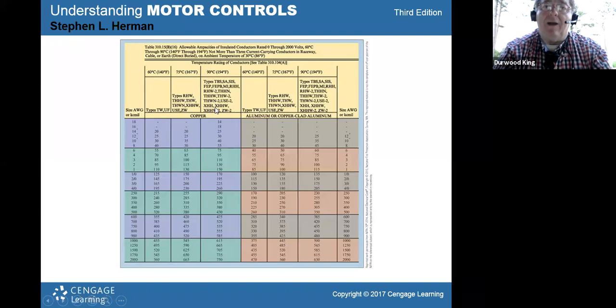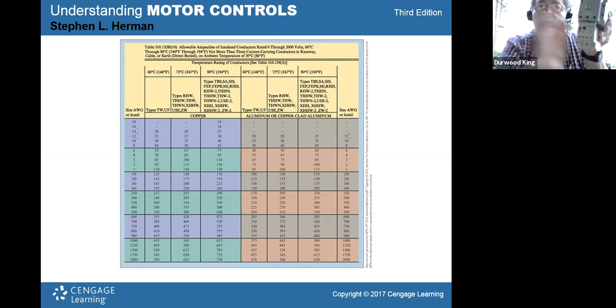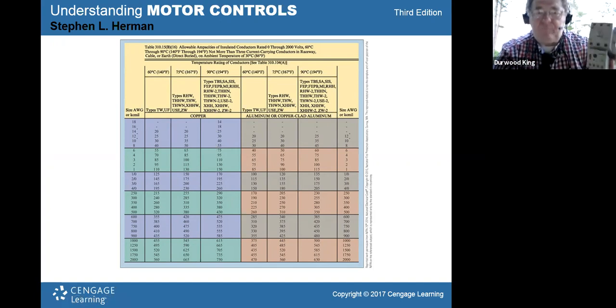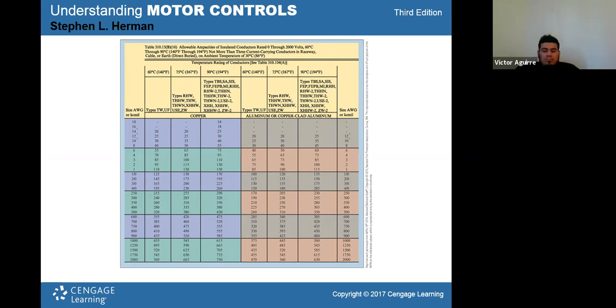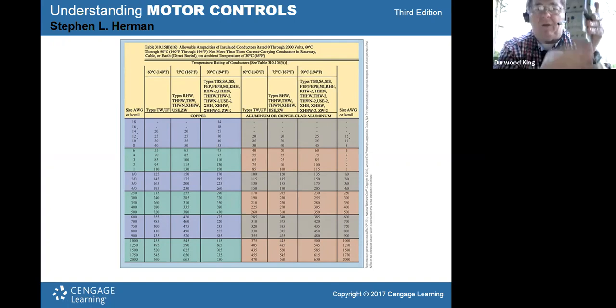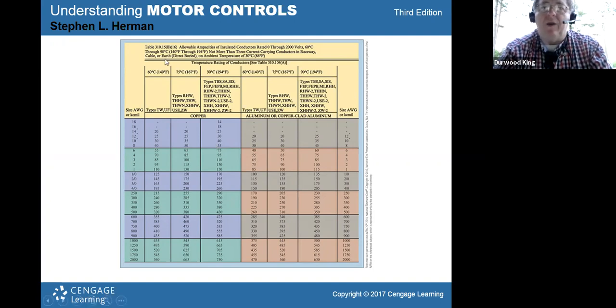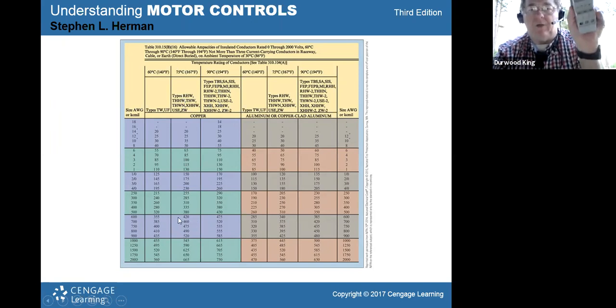But if you use that wire, you can't get the amp rating out of that column, because the terminals are rated one column back. You've got to go with the lowest rating on each end of that wire. So you have the starter here, and then your terminal strip where you're tying in a motor. If it's 75 degrees Celsius because of the rating stamped on here, which a lot of times it is, you've got to use the 75 degree column to rate the wire, even though the wire insulation may be in the 90 column. You've got to fall back to the 75 column because the weaker link is the terminals on the starter.